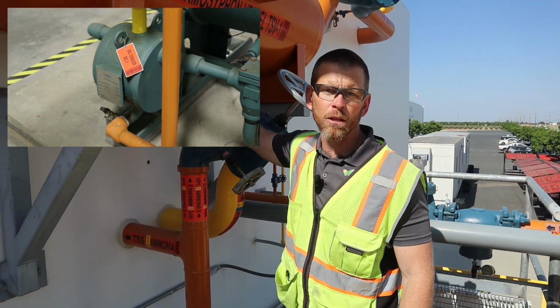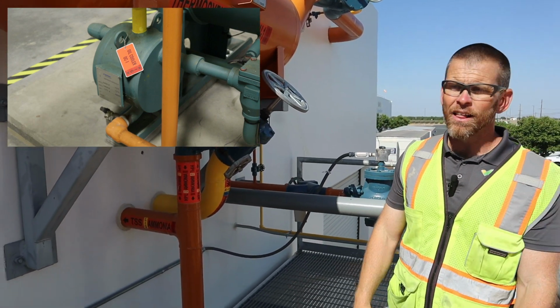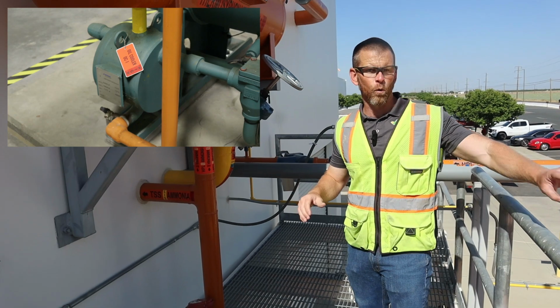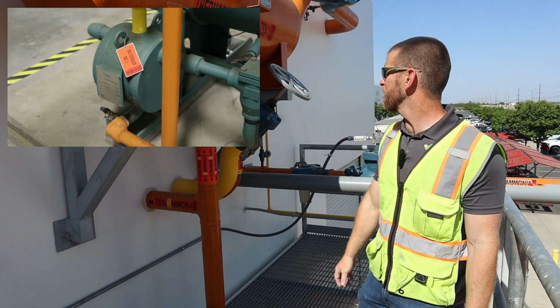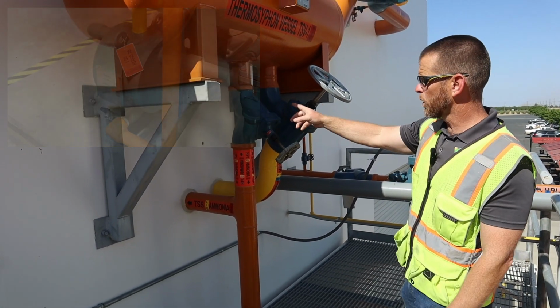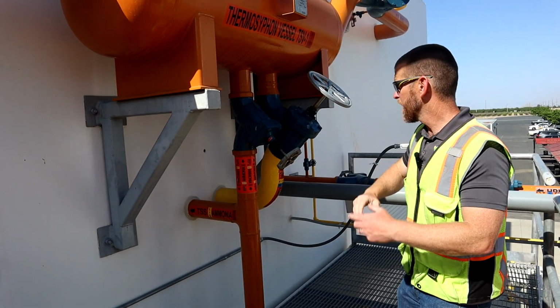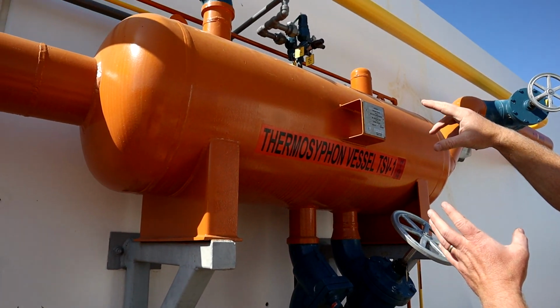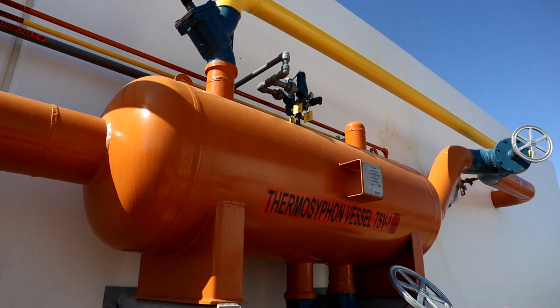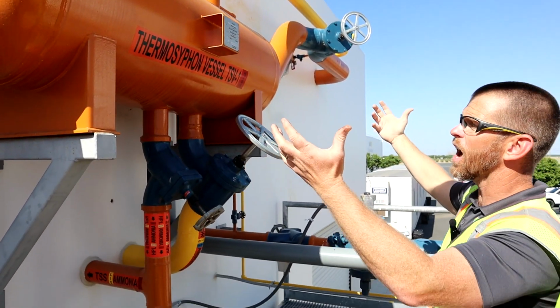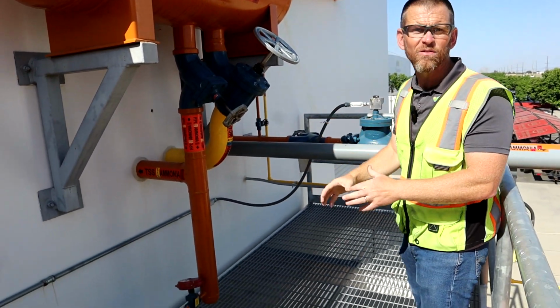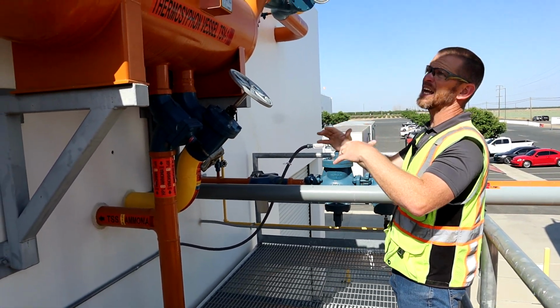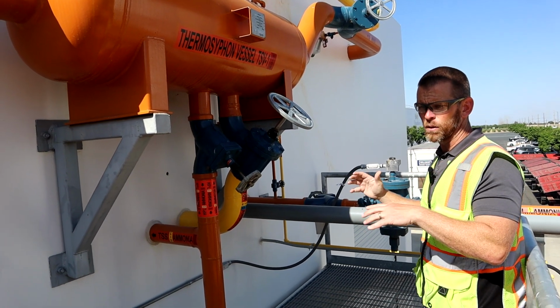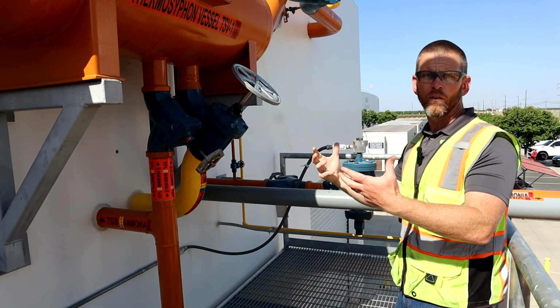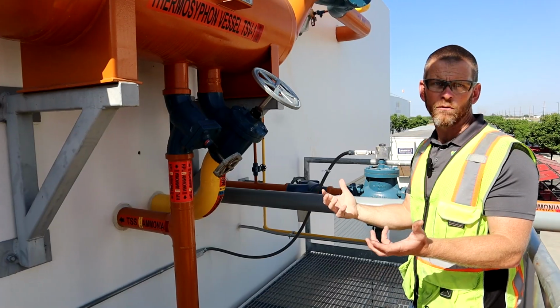And because this is connected to the bottom of the vessels, we say this has priority. That means that this gets liquid even before the receivers get liquid. It is a priority vessel in the system. Vapor that returns from the thermosyphon oil coolers comes through this yellow pipe and is returned to this vessel. And this vessel is vented or equalized in pressure with our condensers through that yellow pipe. So there's not a lot of automation. There's no automation going on with this vessel. It's a very simple vessel, and it works simply through the natural flow of refrigerant by gravity and temperature differential.